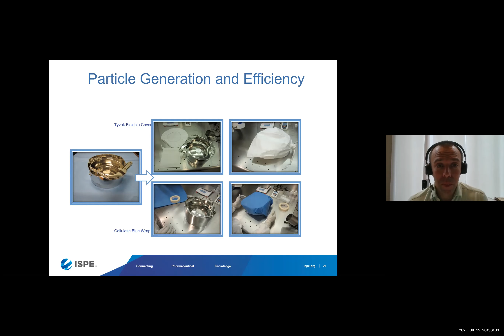We also ran these parts through a sterilization cycle in the autoclave and then measured particles generated during the unwrapping and the time required to unwrap the materials. And again, we saw a minimum twofold difference in particles generated. So that was the particle difference.